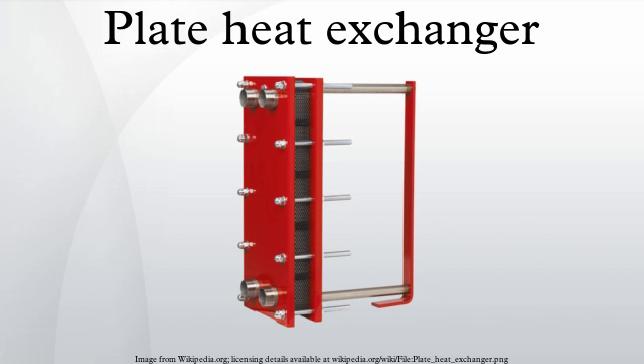The plates used in a plate and frame heat exchanger are obtained by one-piece pressing of metal plates. Stainless steel is a commonly used metal for the plates because of its ability to withstand high temperatures, its strength, and its corrosion resistance. The plates are often spaced by rubber sealing gaskets which are cemented into a section around the edge of the plates. The plates are pressed to form troughs at right angles to the direction of flow of the liquid which runs through the channels in the heat exchanger.